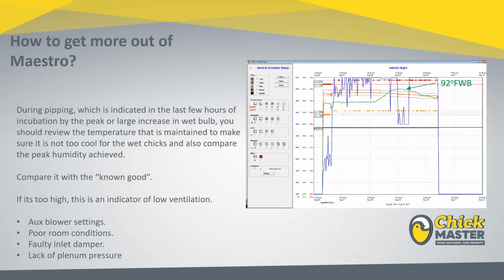So it's a good idea to monitor that wet bulb for various reasons, but in this particular case, what we're looking for is a wet bulb that's not getting too high of a peak. So this is a known good graph. When I compare it to one like this, where we see really high wet bulb conditions that stay flat for a long period, and we're getting as high as a 96-degree wet bulb there, we may find things such as the auxiliary blower settings not correct, or we may find poor room conditions, faulty inlet damper, or lack of plenum pressure. In other words, for whatever reason, we're just not getting adequate airflow through the machine during that time period, and we're seeing really high wet bulb conditions that occur.